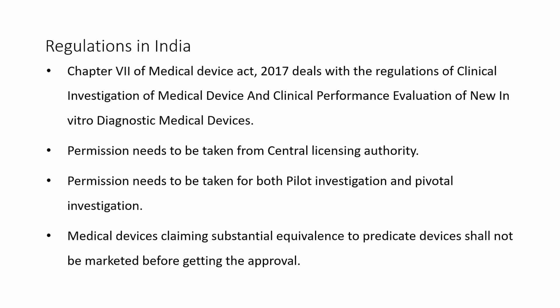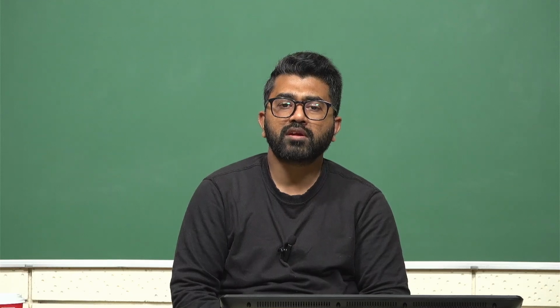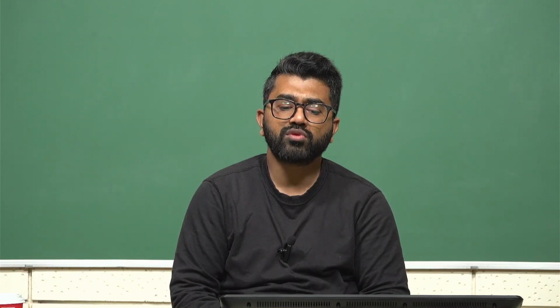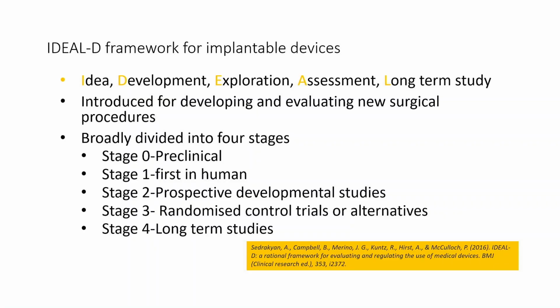Medical devices claiming substantial equivalence to predicate devices shall not be marketed before getting approval. So many of the devices which already exist, which say that they are quite equivalent to what the market has produced, sometimes to bypass the rules of clinical testing, will not get approval that easily. So that's as per the norms of the Indian government, right?